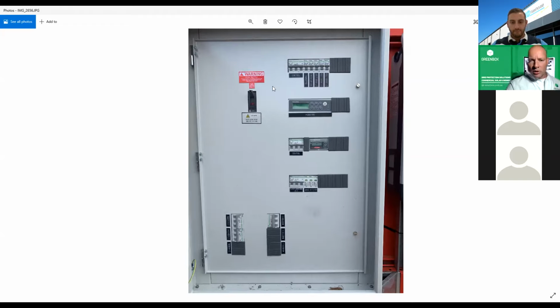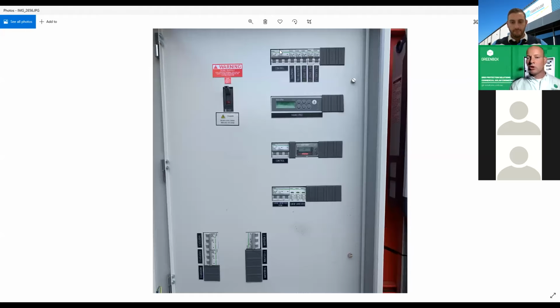We've got a mains control switch, which if you switch off, isolates the whole control part of the board. We've got your voltage references so we can check the voltage levels. Underneath, we're using the ComAp Mains Pro unit. Depending on which DNO you're in, you require different settings, and you might even need specialized settings - let us know what you require. The unit will be pre-programmed and arrive on site as a fully plug and play unit, so all you have to do is put your cables in and you're done.